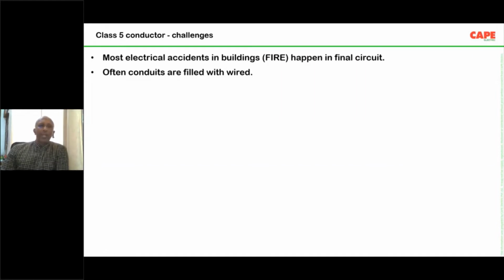Most electrical accidents in buildings happen in the final circuit. Often conduits are filled with wires. What I mean to say is, you know very well, let us say we have a 1-inch conduit, and inside the conduit there are filling factors. You are supposed to fill it maybe 30%, 40%, not more than that. Whereas in most conduits in India, it is completely filled. So when current flows through a conductor, it produces heat, and the filling factors are defined in order to ensure that the heat produced in the conductor is handled very well.